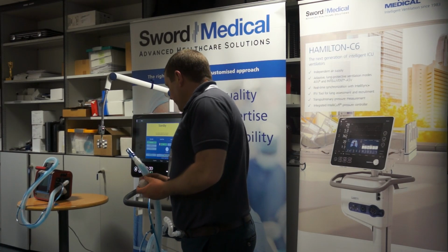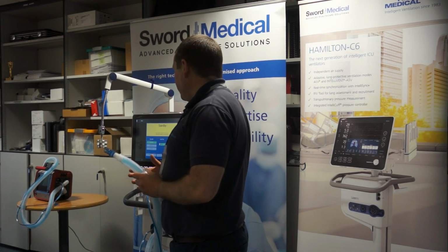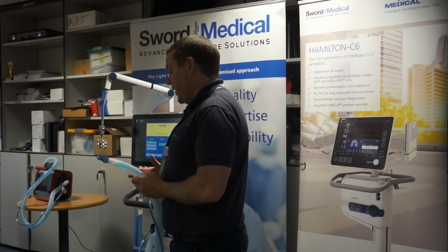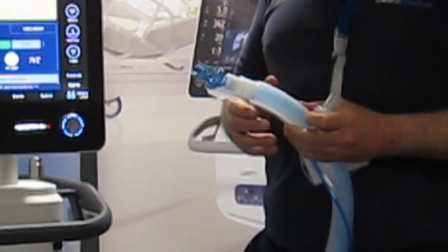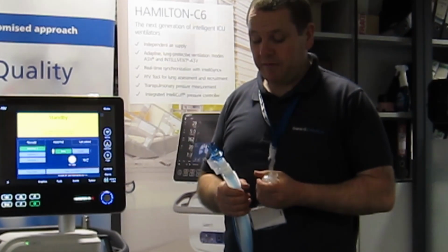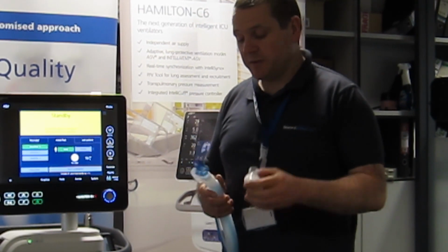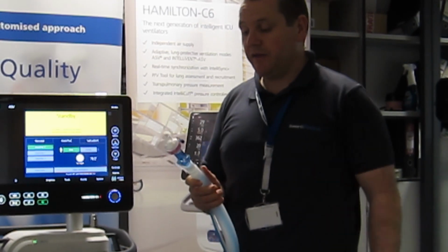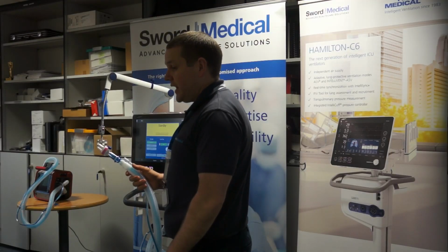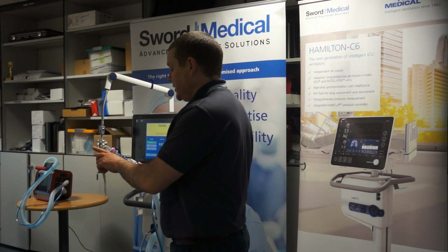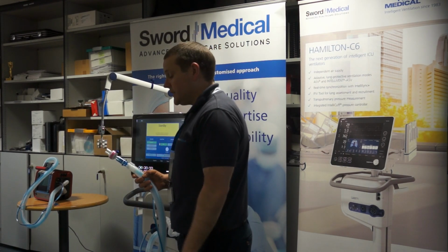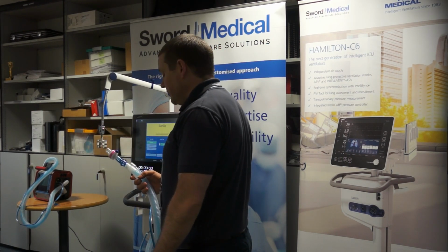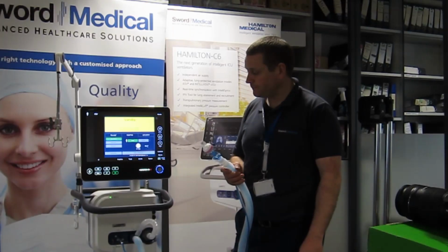So the recommendation for turbine driven ventilators is that you would have a bacterial or viral filter on the inspiratory port or limb, but also with the current coronavirus, obviously you want, very important, to have your expiratory limb also filtered. What we've seen most hospitals do is they're putting their bacterial viral filter here at the flow sensor end, so it's filtering the air going to the patient, but also it's filtering the air coming from the patient, so you're protecting clinical staff and the environment if you have an infectious patient.